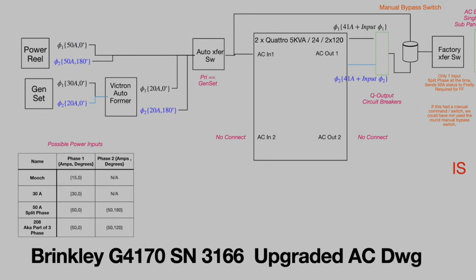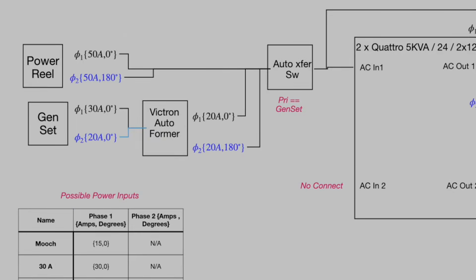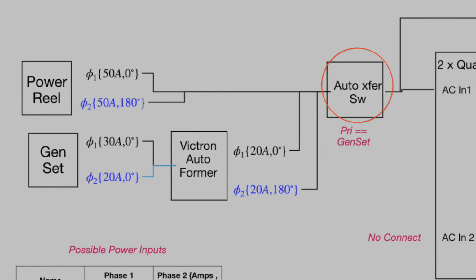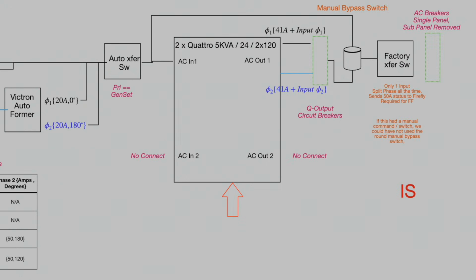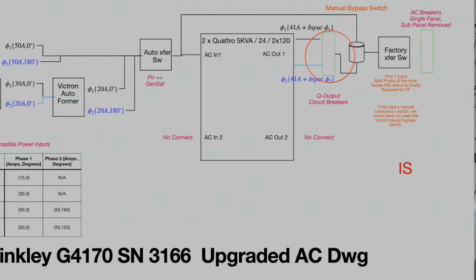This is how your new system will function. Shore power and generator come into an auto transfer switch, a secondary auto transfer switch. Your generator comes through a 100 amp auto transformer, transforms from 120 volts to 120/240, comes in through the auto transfer switch, and then the legs split to leg 1 and leg 2 of the Quattros. Output of those goes into a 50 amp load center with a 50 amp breaker. In that load center there will be a Midnite SPD, a surge protection device. Then the output of these will go into your factory automatic transfer switch and onto your AC load panel.